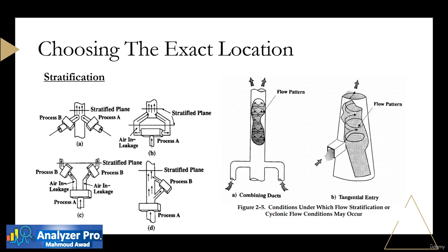But what is stratification? Flowing gases are generally well mixed, but stratification can occur when there are differing temperatures or when dissimilar gas streams intersect. Several conditions where gas concentration stratification may occur, such as air leaking into a duct, the combining of 2 process gas streams into a stack, or the reintroduction of scrubber bypass gas into the flow, can all result in such stratification.